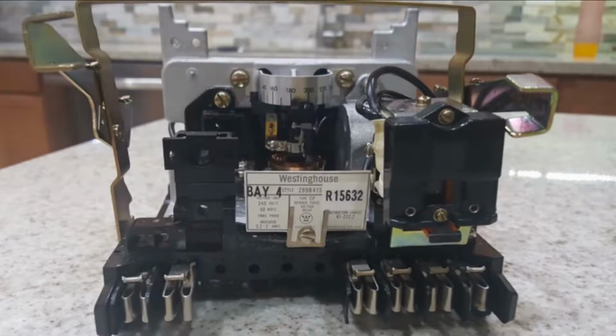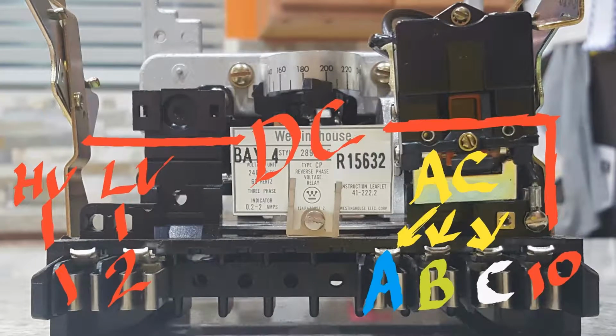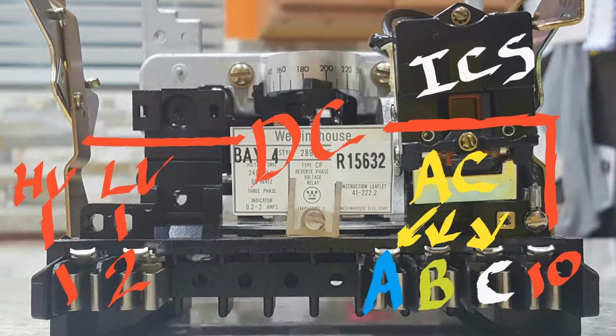Here's a look at the relay out of the case. It's important to note that we have AC and DC present on this relay. You'll notice the 6 tabs. You can see the DC on the left and the right with the A, B, and C phase input AC in the middle. Let's take a look at the settings and adjustment on this relay.